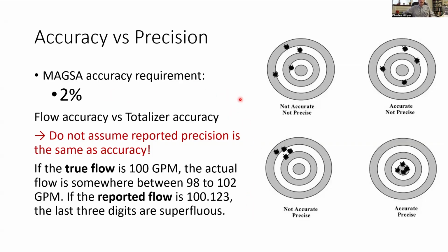Now, this 2% accuracy requirement is important because what you see when you're looking at the flow is not exactly equal to what's happening. For example, if your true flow is 100 gallons per minute, then the flow that's reported to you is somewhere between 98 and 102. So if you're seeing 98, then the flow rate could be 100, it could be 99, it could be 101. If you're seeing 102 on the flow meter, then the true flow rate is somewhere around 100 or 101 or maybe 103.